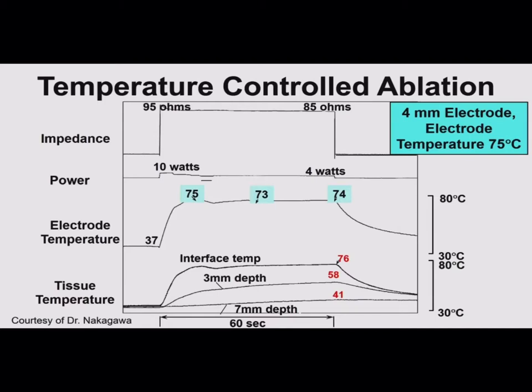This slide from Hiroshi Nakagawa shows that in the past, with non-irrigated catheters, we often did temperature-controlled ablation — setting the maximum temperature, here 75 degrees. We don't set it to 100 because we're underestimating the tissue-electrode interface temperature since our thermistor is proximal to the electrode. So with a 4-millimeter electrode set to 75 degrees, we deliver energy and heat the electrode to about 75 degrees. The power here is relatively low — 10 watts — and when using temperature control, the system automatically decreases power to maintain that temperature, giving a small amount of power and heating it up to 75 degrees to create about a 3-millimeter lesion.